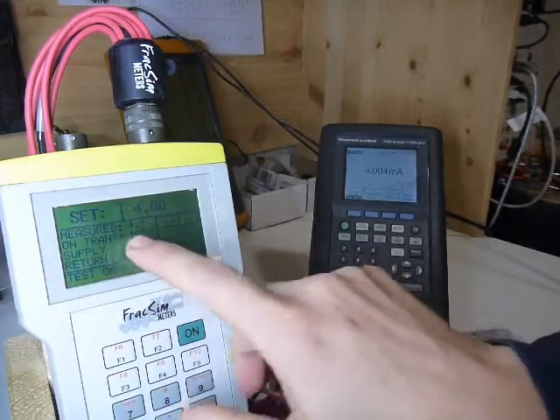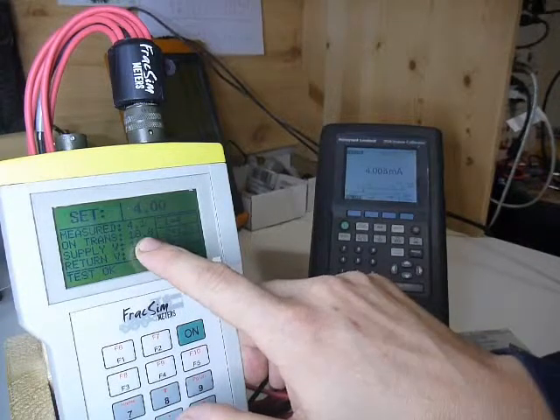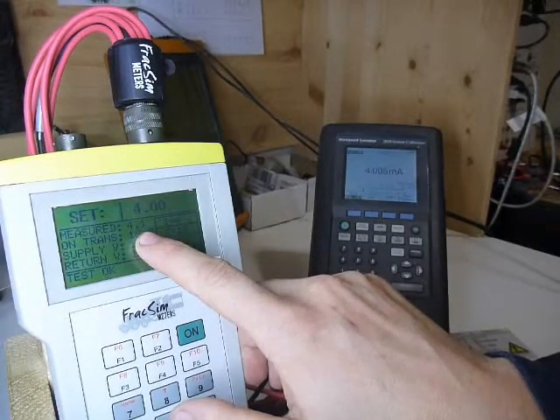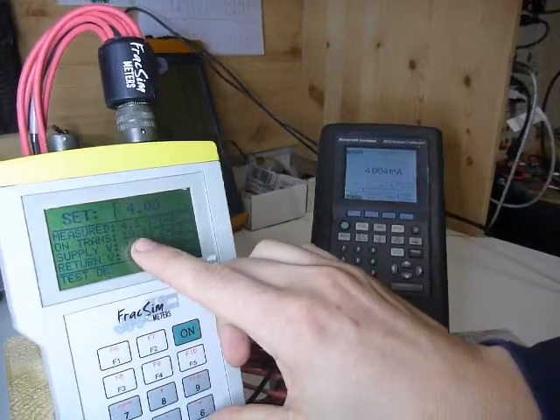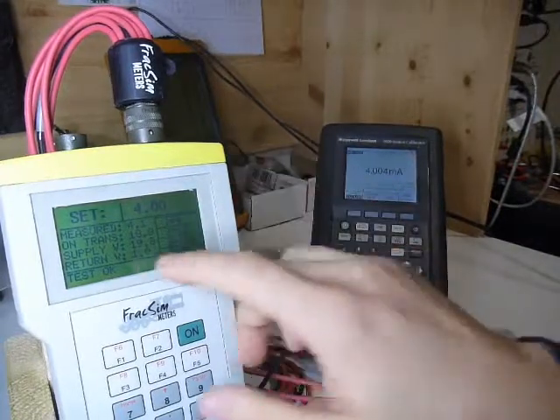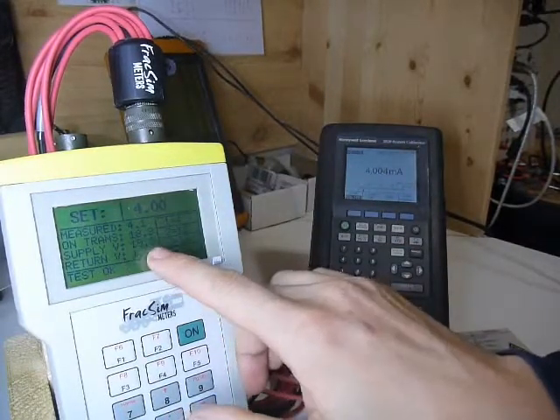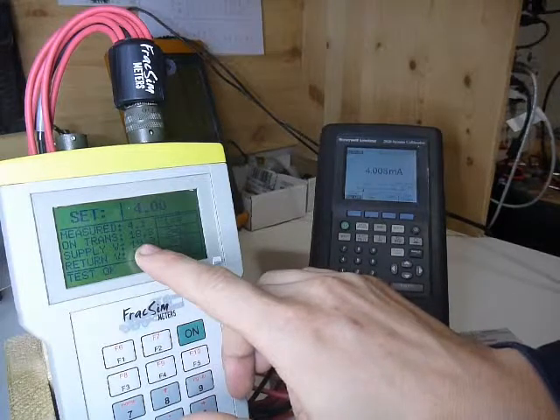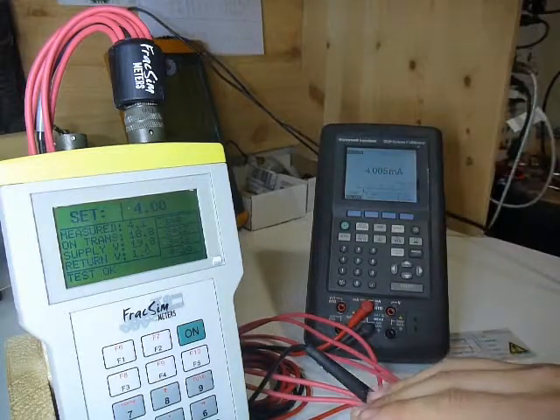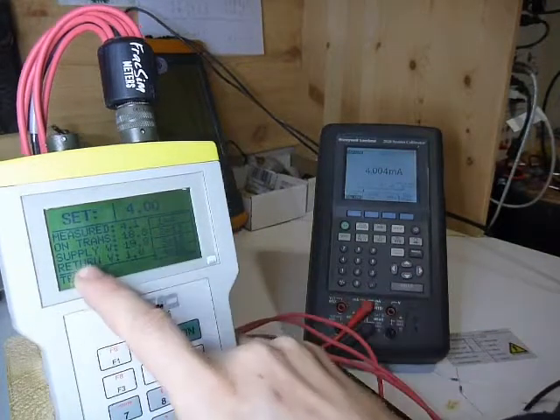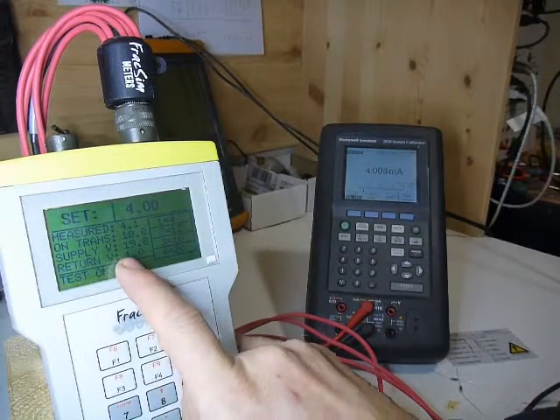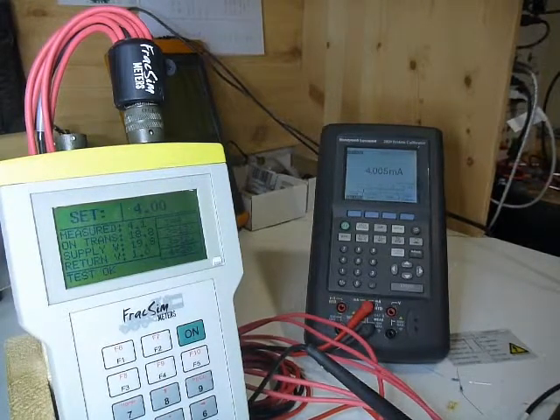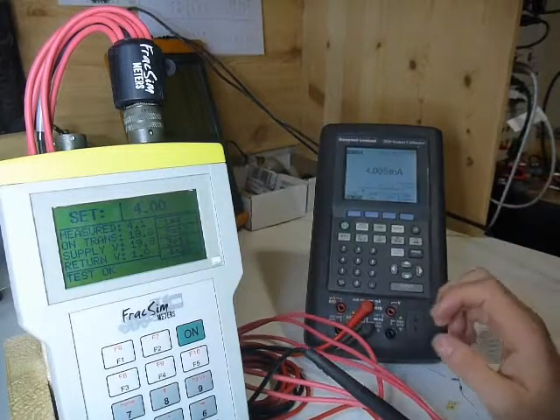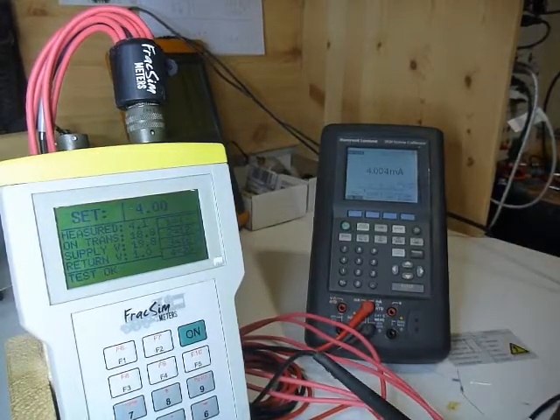On the transmitter, now this is a voltage measurement. This is the total voltage on the transducer, or what would be the transducer, what is now the Fracsim. So that'd be the actual voltage across the Fracsim. The supply voltage is 19.8, and that would be the actual voltage from the unit to frame ground. And this here, return voltage, this return voltage is the drop from the return of the meter to frame ground. So it's actually making 3 different voltage measurements.